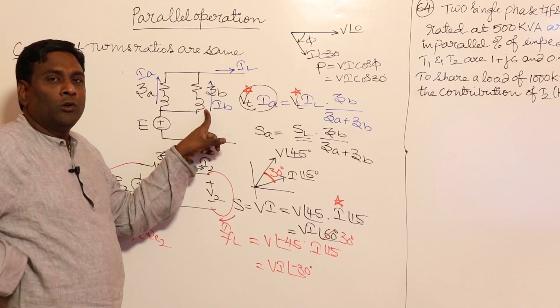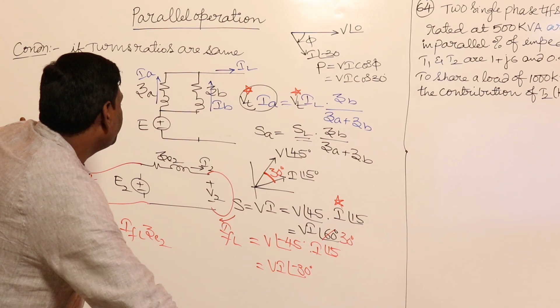Now, for example, logic is simple. For example, this full load current is 10 amperes and this full load current is 5 amperes. Now my impedances should be such a way, because in parallel combination voltage will be the same. So whenever this is operating at full load, at the same time if the other is also operated at full load, then 10 plus 5 can be 15 amperes.